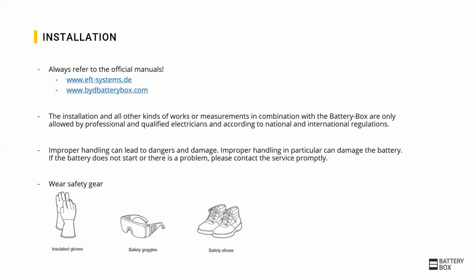After making sure the configuration is correct, we will now look into the installation of the product. For the handling of the battery box, please always refer to the official manuals by BYD, available again at the stated web pages. The installation and all other kinds of works or measurements in combination with the battery box are only allowed by professional and qualified electricians and according to national and international regulations. The handling of the battery is held as easy and safe as possible, but please be aware that improper handling could damage the batteries and lead to dangers.